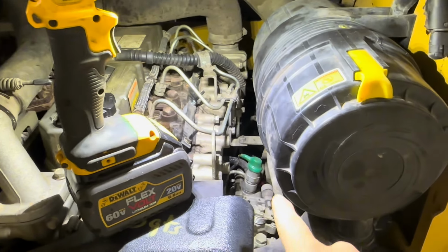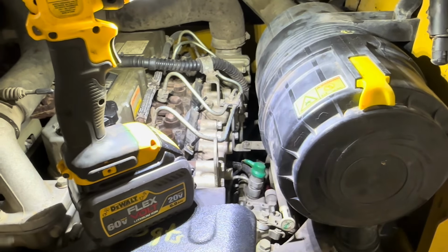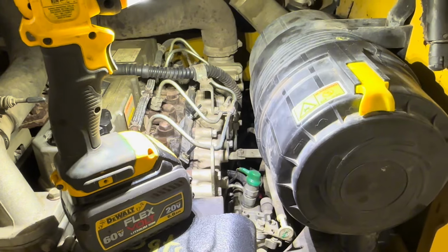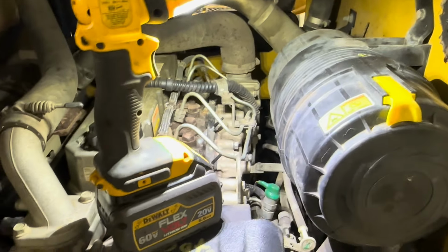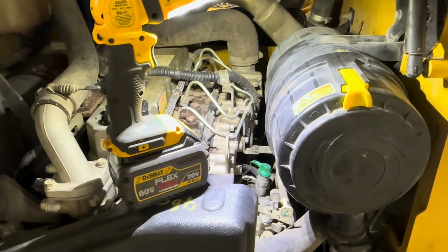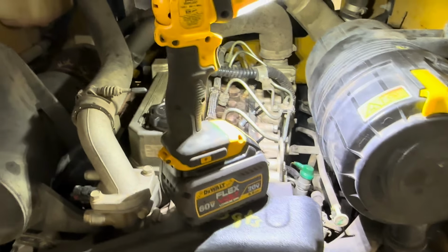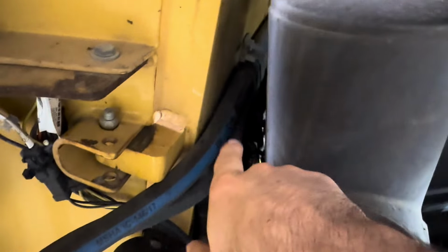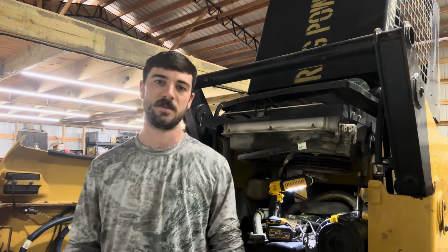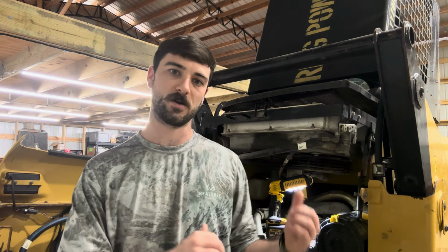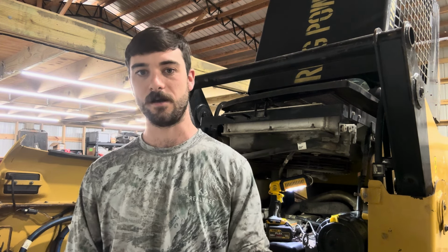Now, if you do have power to here and that's working correctly and all your circuitry upstream is working properly, such as in my case, the next thing is actually kind of back to where we were, where we're getting power for our high voltage side coming off that cold start relay over here on this wall, but nothing on the control side. So then the next thing, if you're in the same spot that I am, is okay, what's going on? Why is that circuit not getting kicked on or being commanded on?